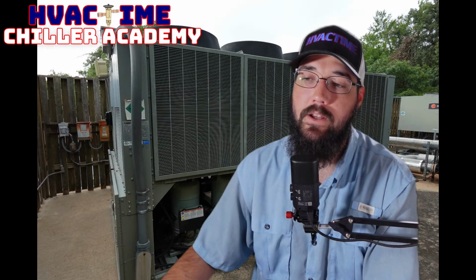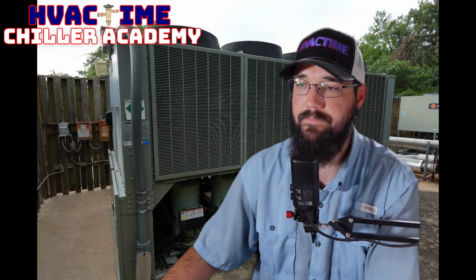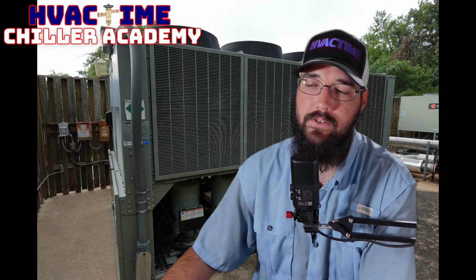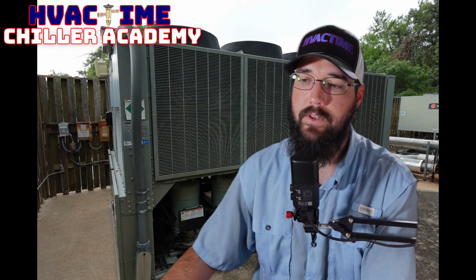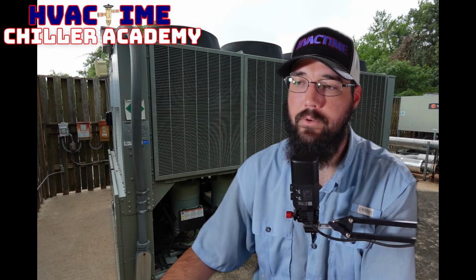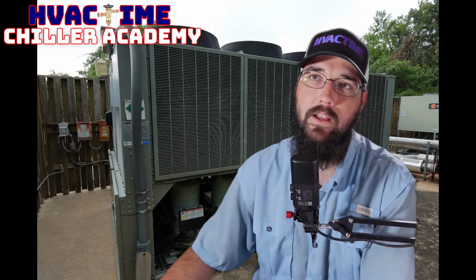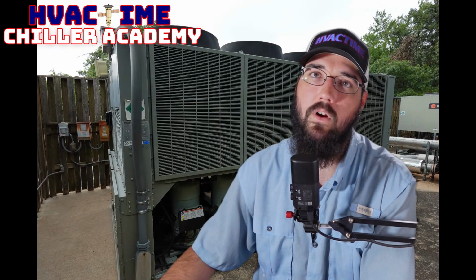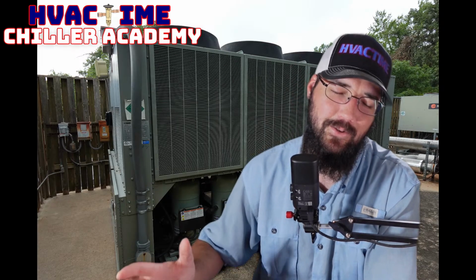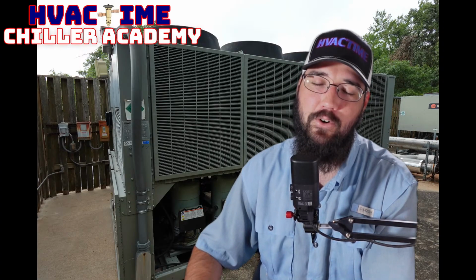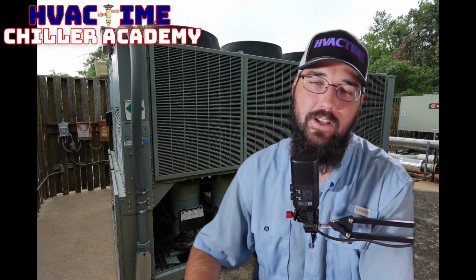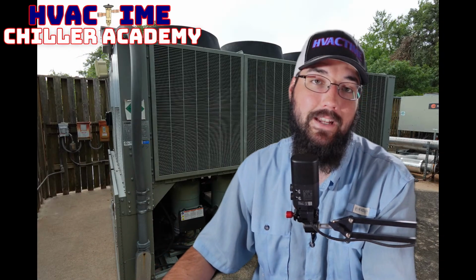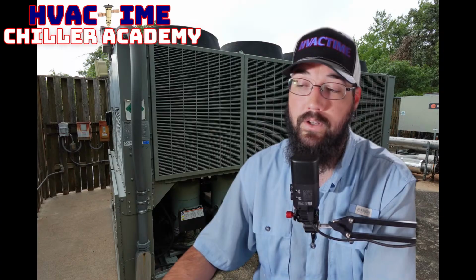Either way, yeah, that would be my assumption, Tom, is this is some kind of process. And if not, then they're showing their lack of education, because you don't do that with motors. You want to keep them, especially with compressors, you want to keep them online. That is more efficient to let them run than have them do a inductive. Thank you. Inductive loads. That's the word. It's far cheaper with inductive loads to allow them to stay online than it is to have them constantly have to turn off and on based off of them being an inductive load to begin with. They vary heavily and they require a lot of energy to get rolling versus a small amount of energy to stay online once they are, compared to getting turned on.